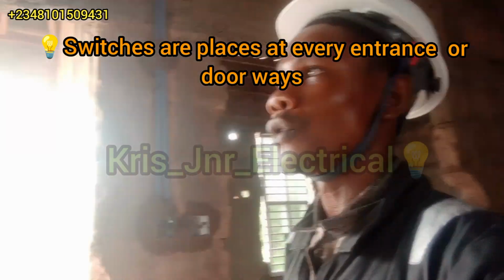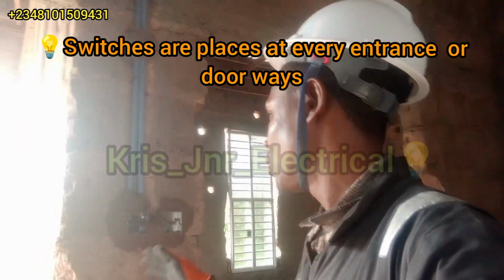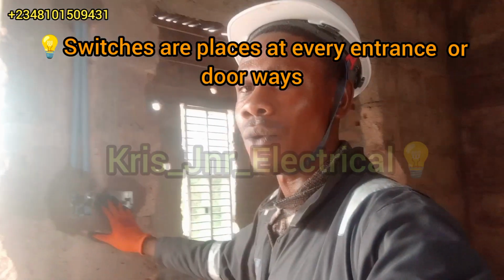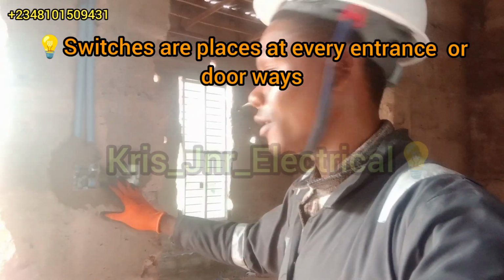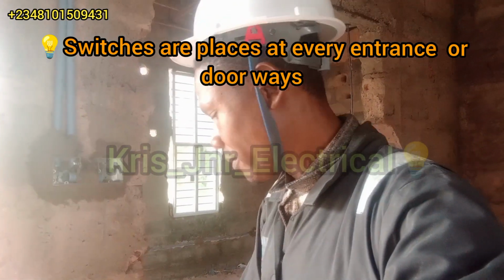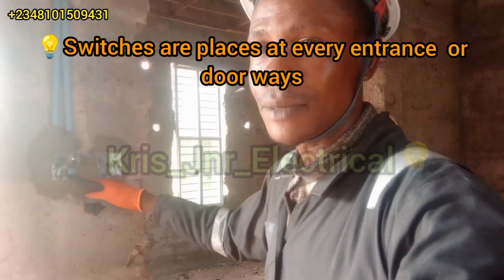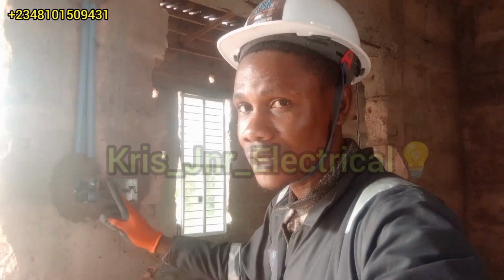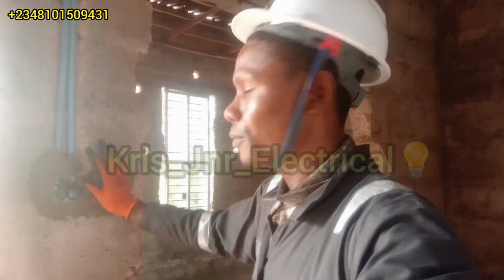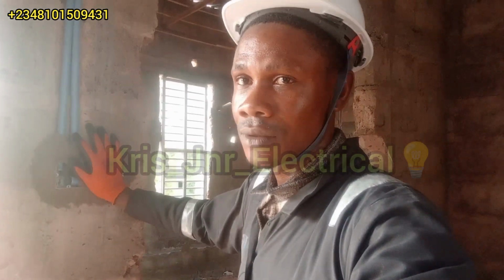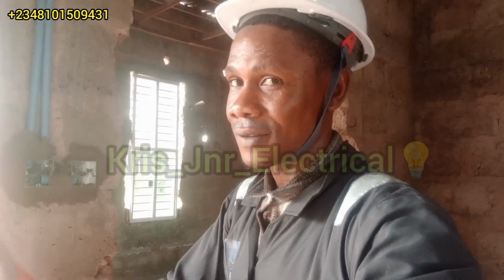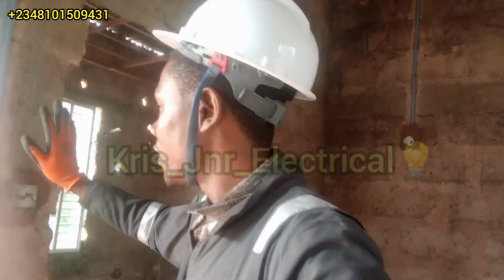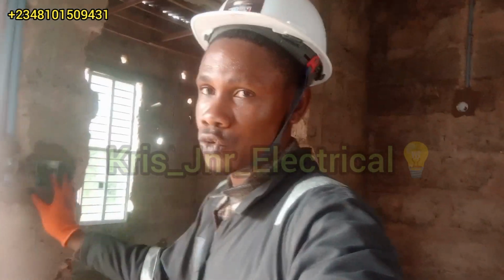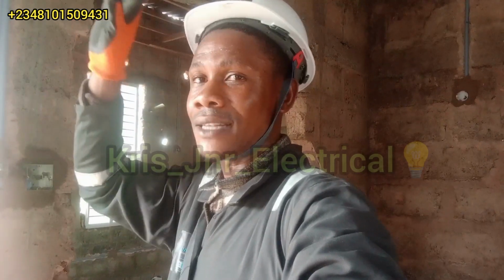You can decide to position your designer lights wherever you choose to. So these are the switches here. They are well placed. I used my measuring tape to take the position. The measurement from the floor level to this point here is about 1,200 millimeter, that's 1.2 meter. That is the position of all your switches. Your sockets are about 45 centimeter from the floor level. So these are switches here for the lighting points.